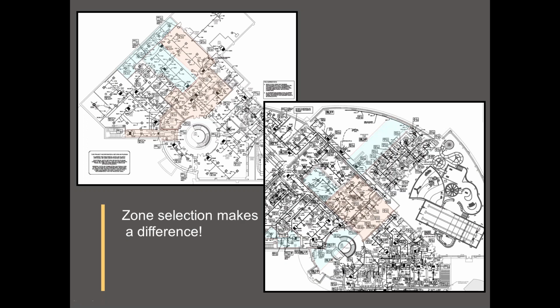If you think about the way these zones are connected, and we'll just start with the pink, this is a below grade floor. Everything in the pink area is essentially a core or an interior zone. There are no exterior exposures except a little bit here and at the lower level, but that's adjacent to earth, so it's not exposed to the outdoor conditions. Similarly, in the upper level, this is a completely interior zone with perhaps a little bit of roof exposure, but this outdoor unit was a heat recovery style.